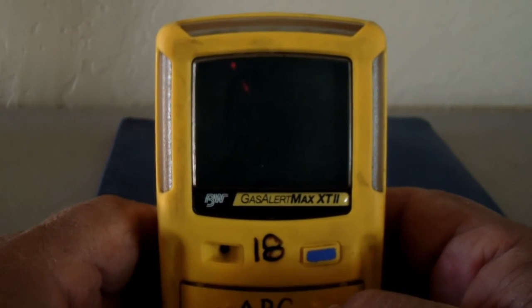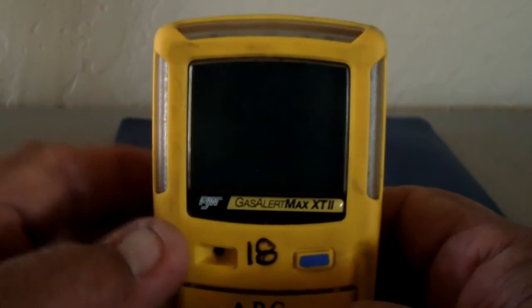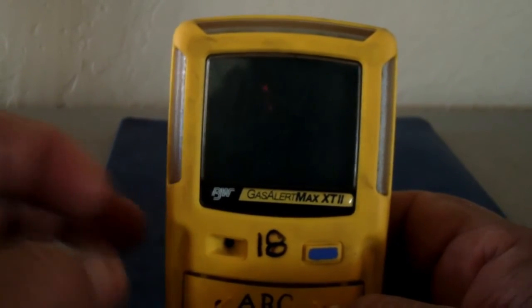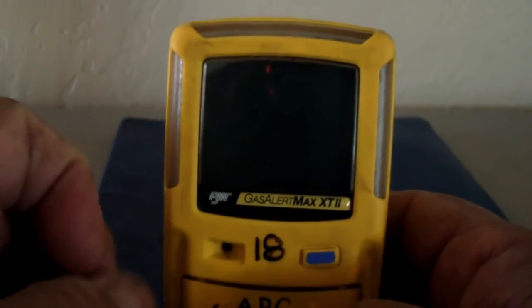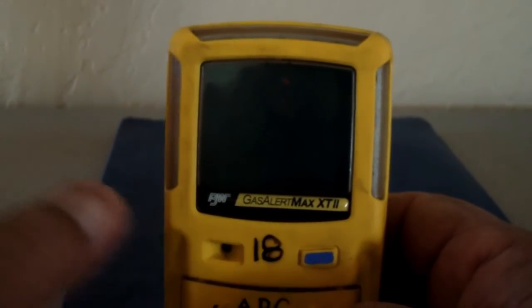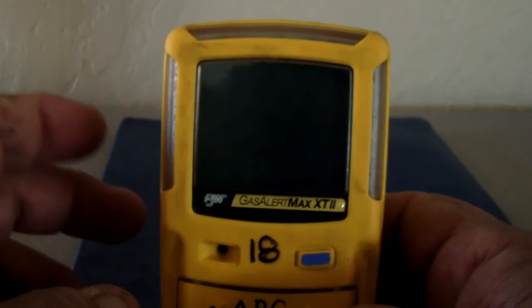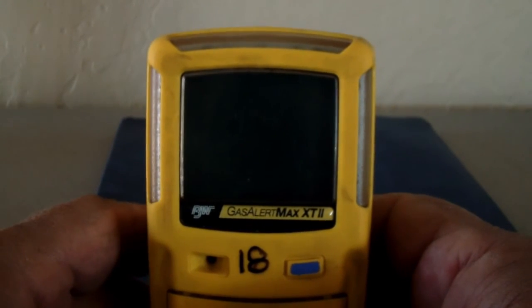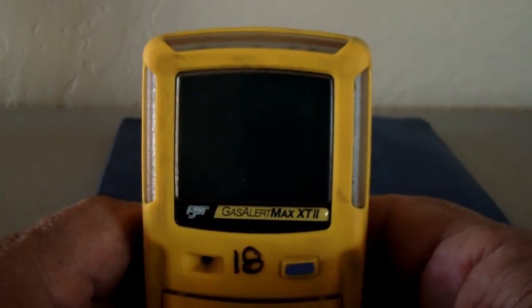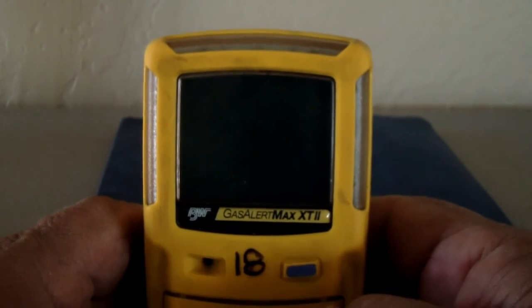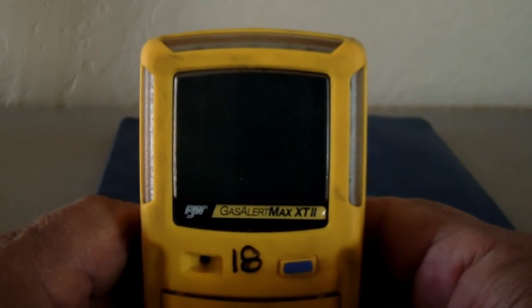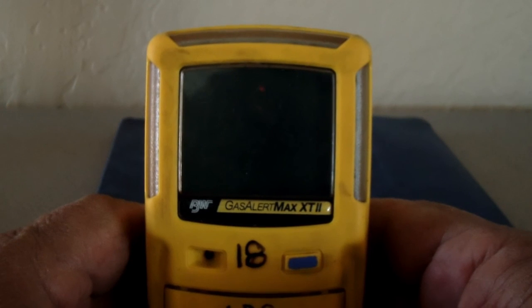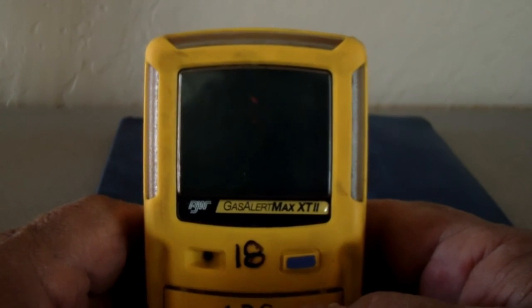So that's how we need to bump this thing in the morning. Turn it on, let it warm up. We're going to go ahead and add the gas. We're going to make sure that our sensors all stabilize on the readings that are on the cylinder, and then we're going to check the peaks, right? And then we're going to clear those peaks so we don't see those later in the afternoon or later in the day.